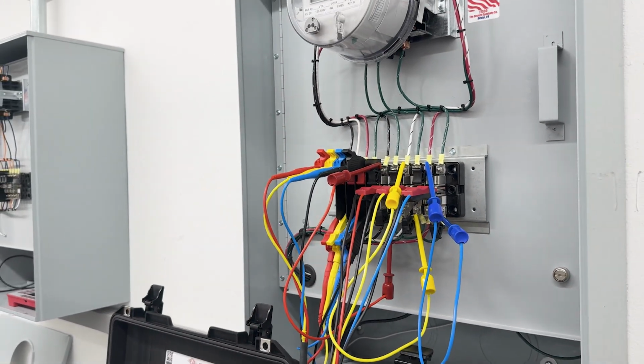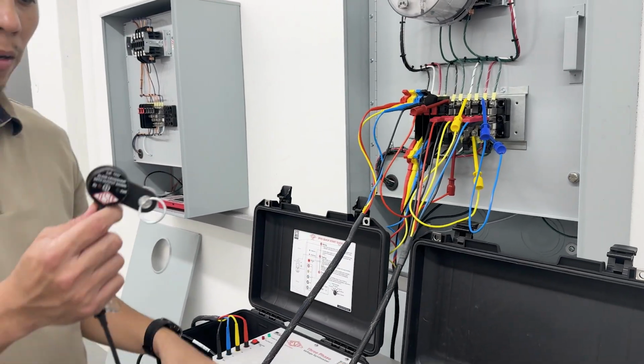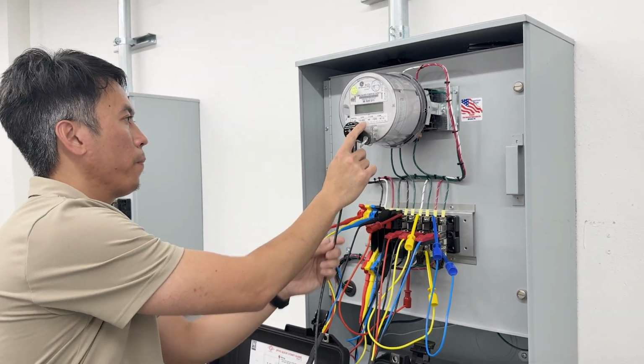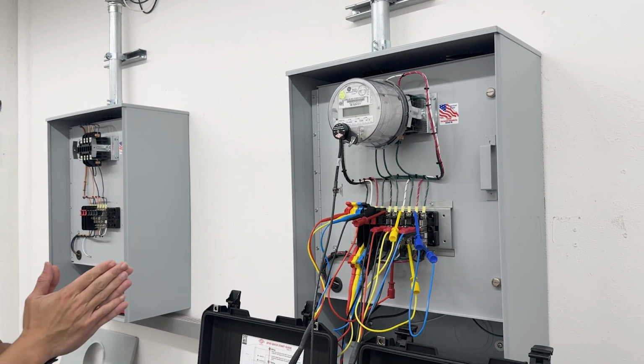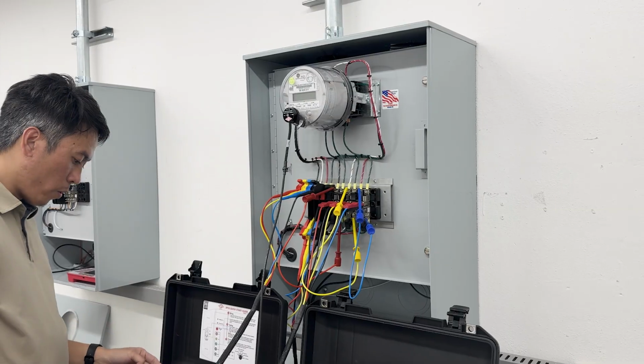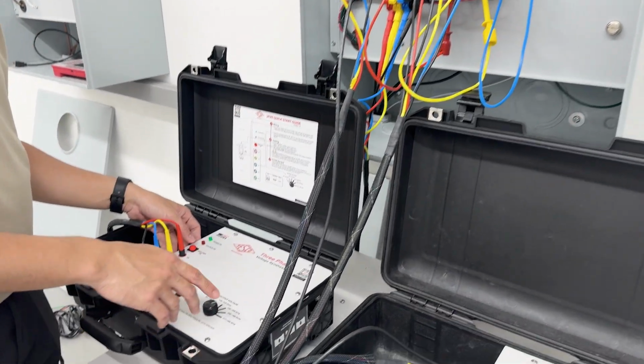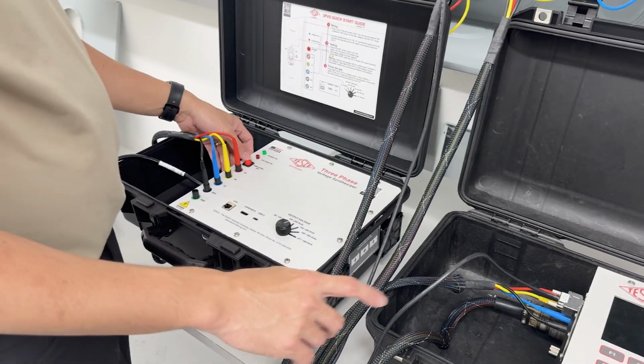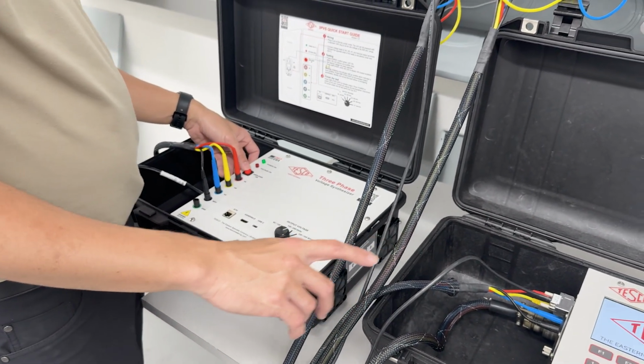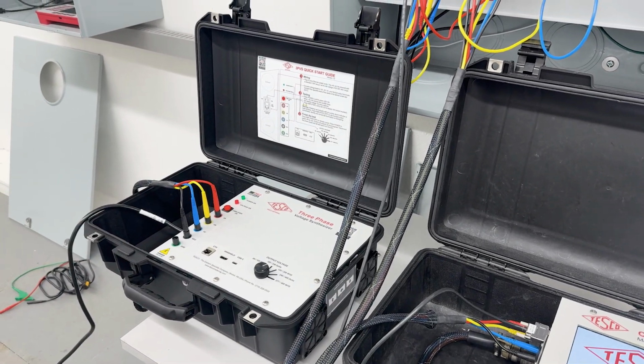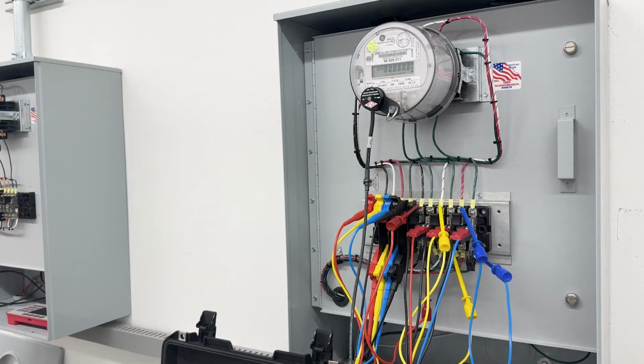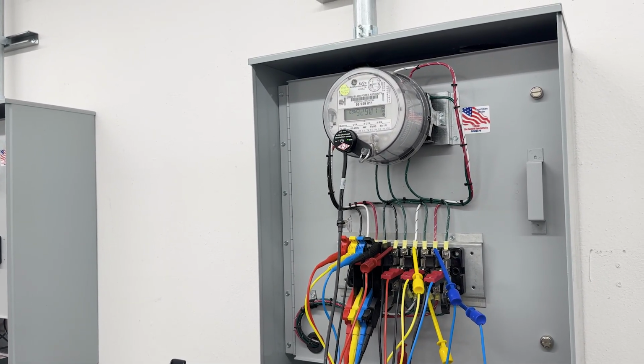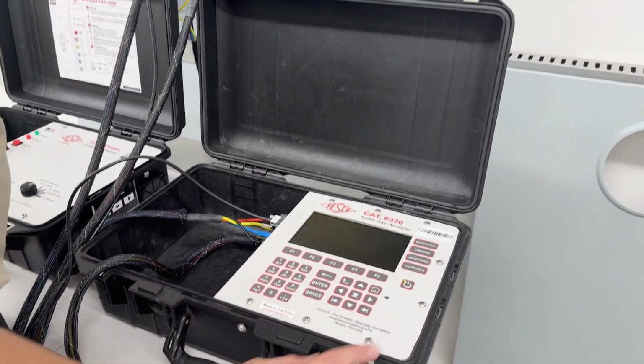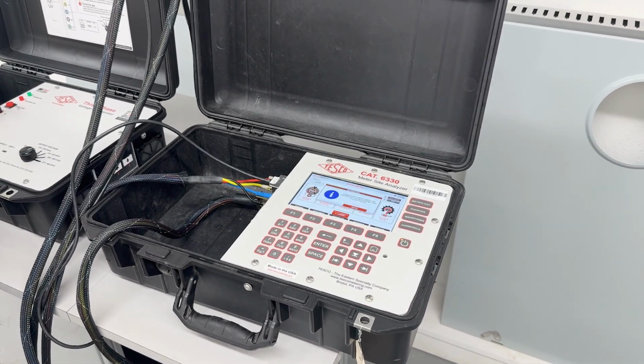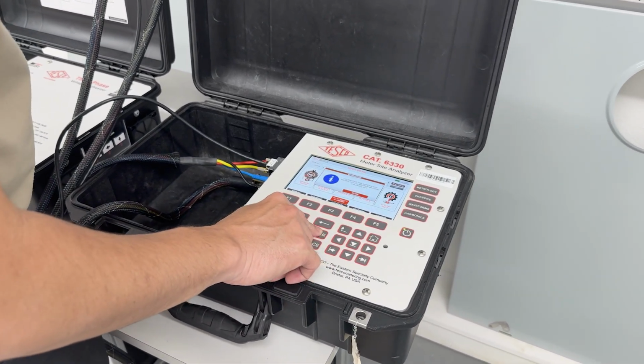And the last item for the setup is grab our optical probe on the meter. Okay, it looks good. So we're gonna power it on using the 6440. We pick voltage config through the rotary switch. And then, okay, we're gonna turn it on. We can see it's powering up the meter. Okay, and so in here, we turn on the 6330. Okay, there's the beep as well. I'm just gonna click enter. It tells something about calibration.